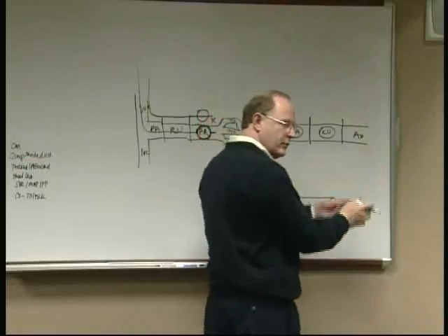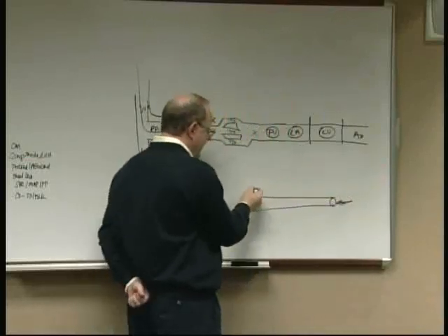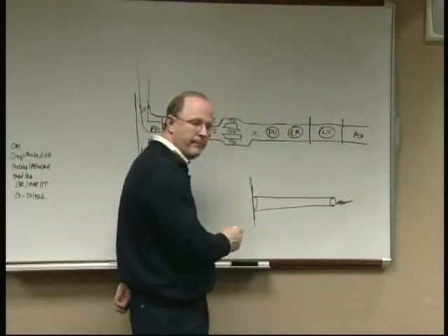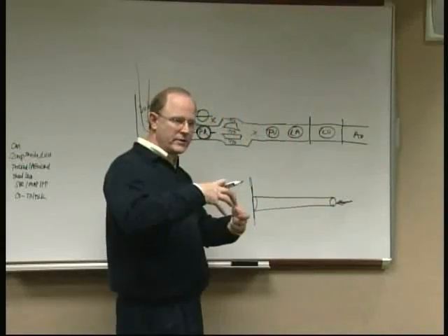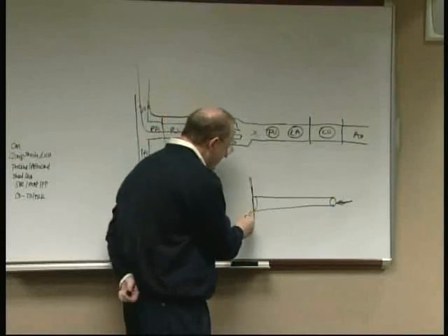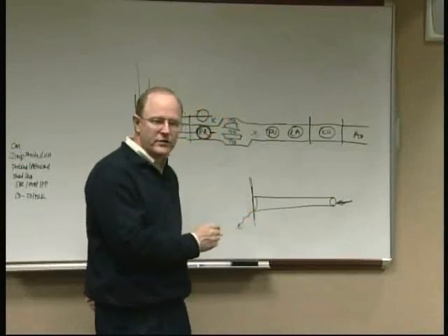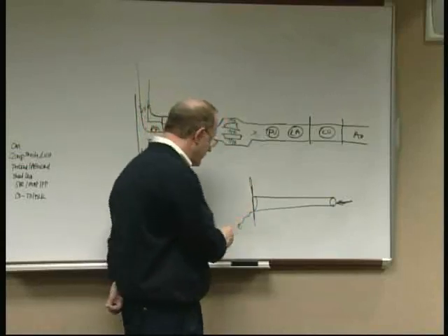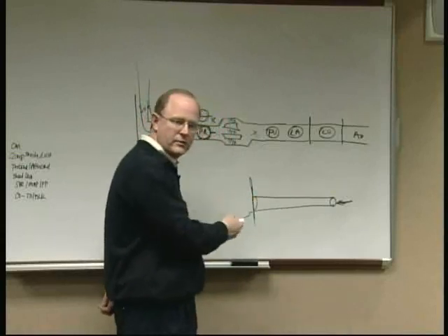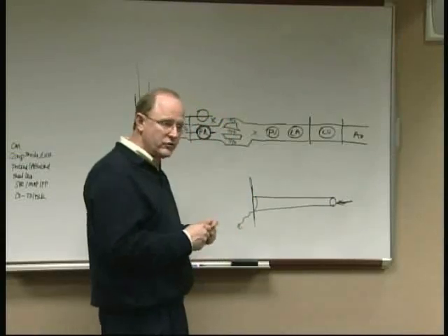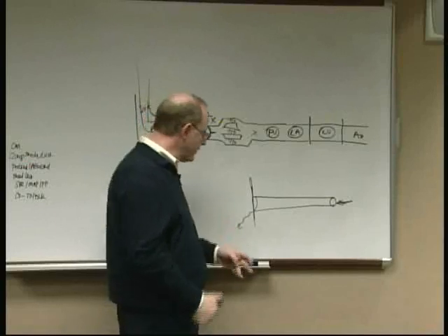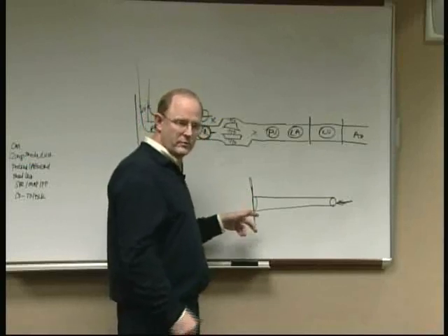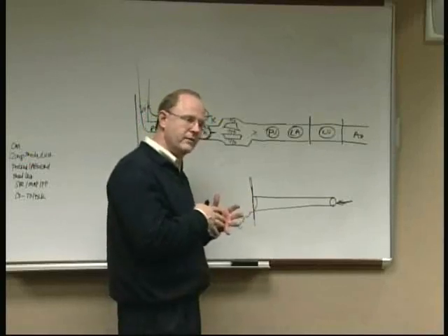It pushes the whole column back, and I have a membrane here, like a drum, and it deflects the drum, and I have a little device with a little electrode that measures how much deflection there is on the drum, and depending how much deflection there is, it tells me how much pressure there is pushing on it. So whenever you set up your transducers in the coronary care unit, you're setting up your drums that you're pushing against with your fluid-filled catheter.